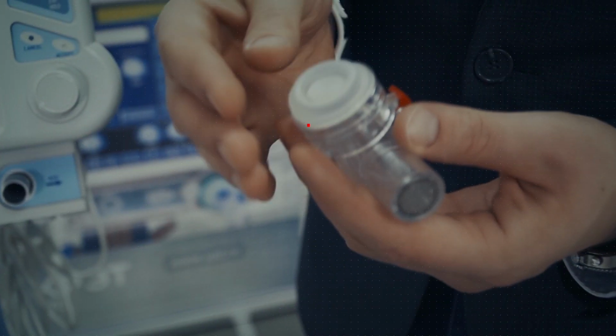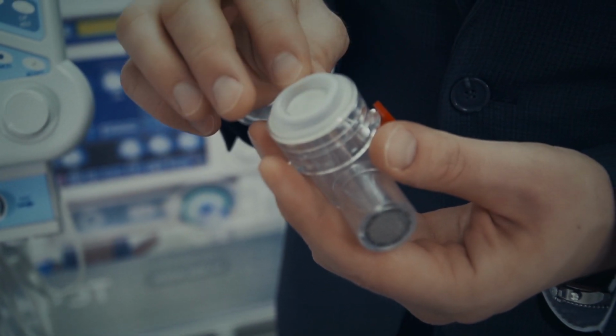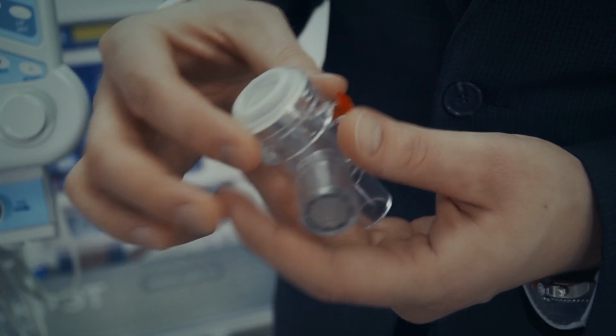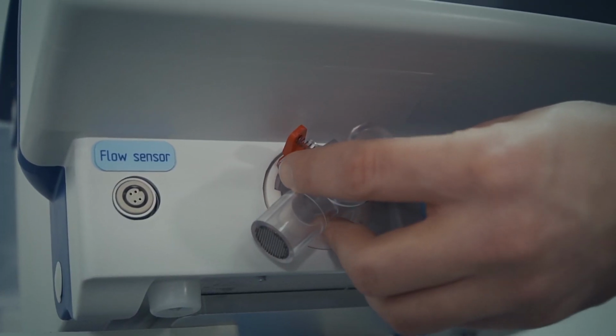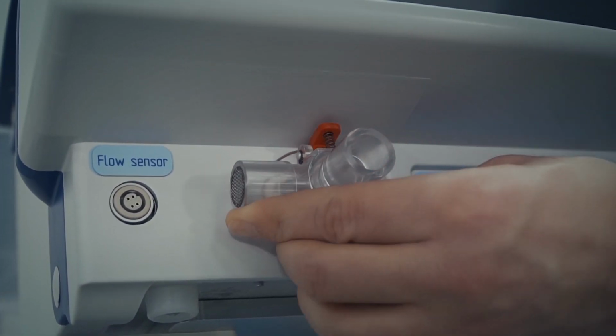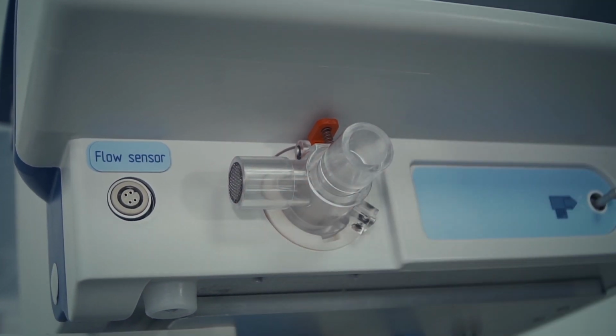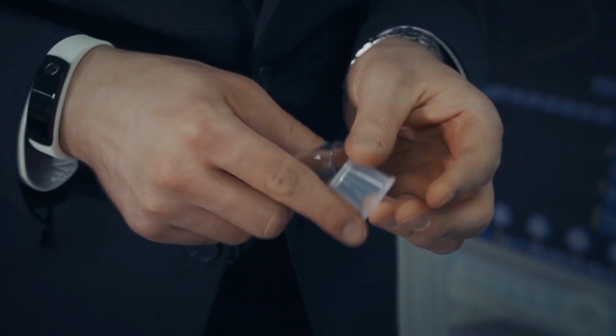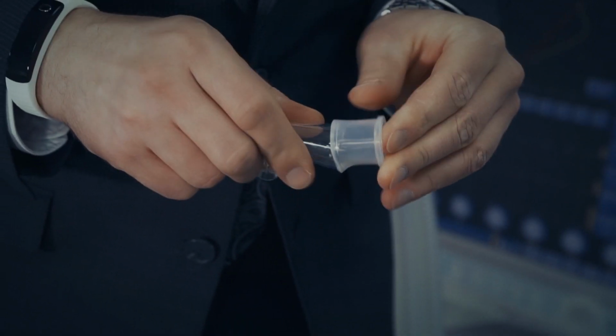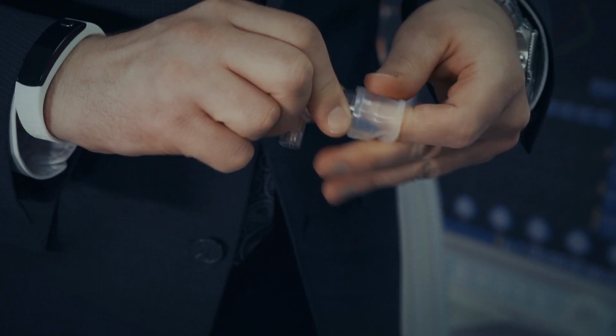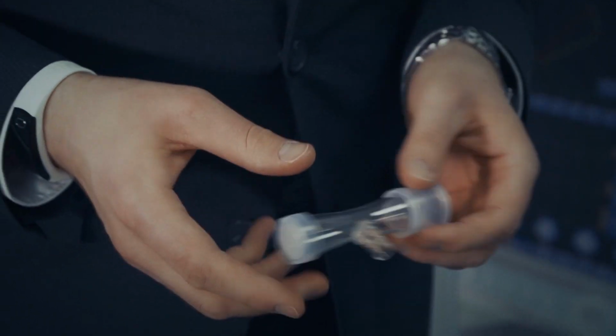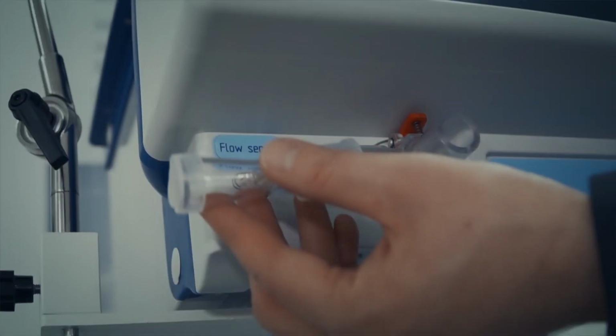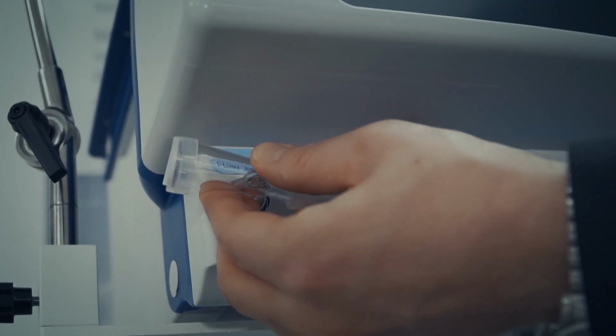Carefully install expiratory valve diaphragm on the valve body, making sure that the diaphragm metal disc is outside. Insert expiratory valve into the ventilator body and rotate clockwise until it engages. Install metal grid and silicone cap to one side of the flow sensor, with the trade name applied. Install silicone sleeve on the other side. Install flow sensor into electric connector near the expiratory valve.